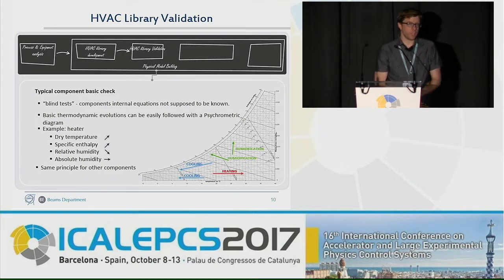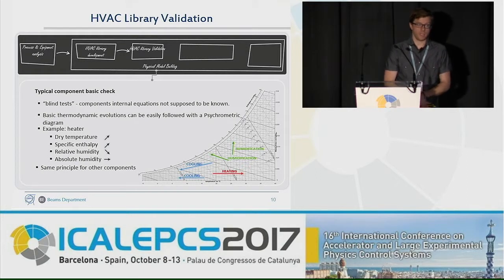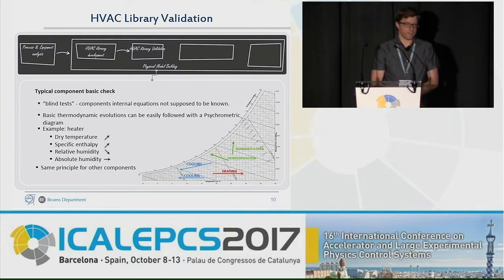So for example, a heater, you would expect the dry temperature and specific enthalpy to increase, the relative humidity to decrease, and the absolute humidity to stay the same. And we check those against the psychrometric diagram.